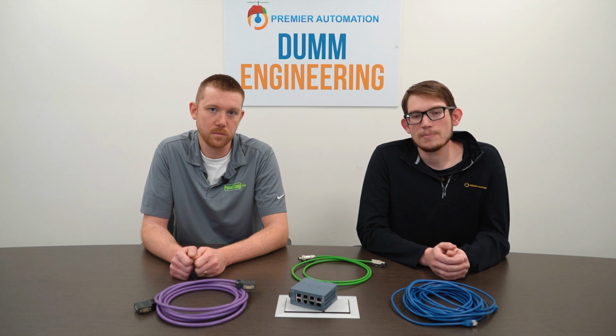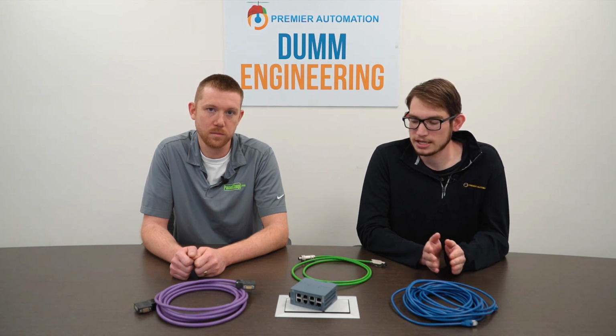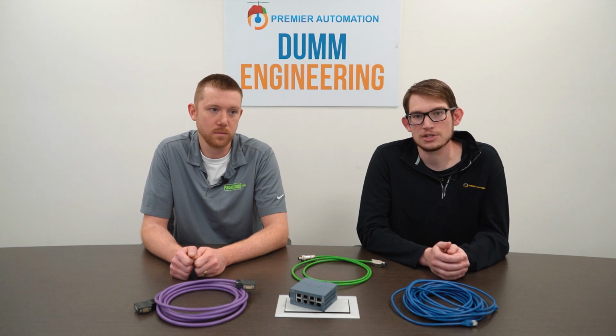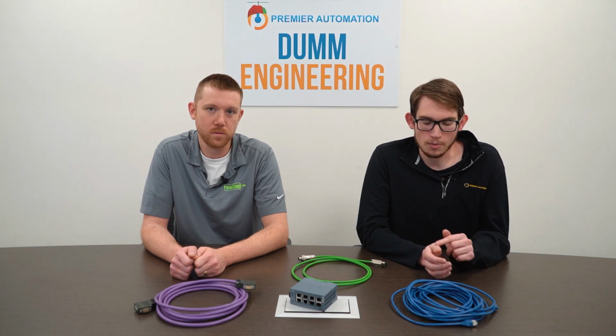With Profibus, they use repeaters to split up the signal. And in cases of Profibus, the network has a topology of either a line where each device connects to the other one, like how Stoops mentioned the resistor on the end defines the end of the line, or they can be a ring topology, which allows them to talk in one big circle and have some redundancy.